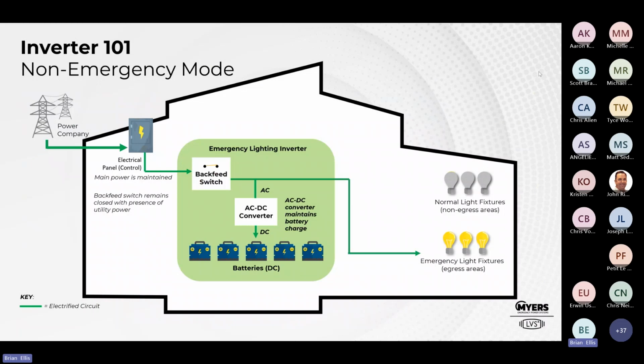Okay, if there's no more questions, let's roll back. So I kind of want to take a step back and just say, okay, let's look at our emergency system as a whole and put together the inverter as well as the bypass relay, okay? And then we can move forward. So what we have is our utility that's feeding our electrical panel. And then that's now connected to the hot and the neutral to our emergency lighting inverter, which is in green here. Under normal circumstances, this backfeed switch is closed and the power flows through freely to the emergency lights.